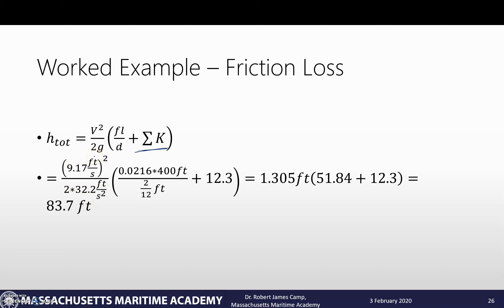0.0216 times 400 feet divided by 2/12 of a foot - those will cancel out giving us a unitless parameter - plus 12.3. Those are both unitless, we can add them together. Once we do that, we're going to end up with a total frictional head loss of 83.7 feet.